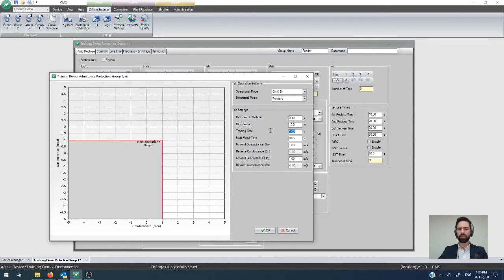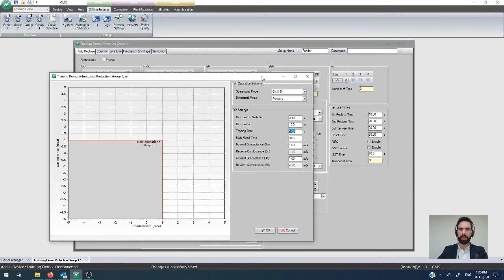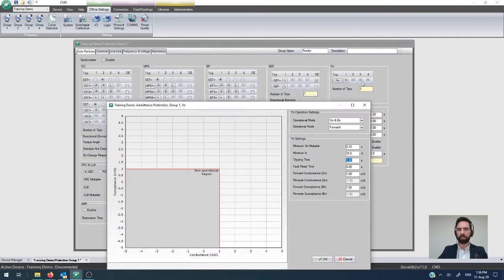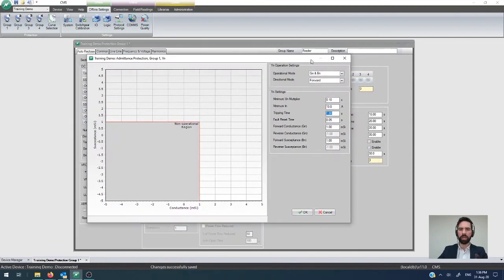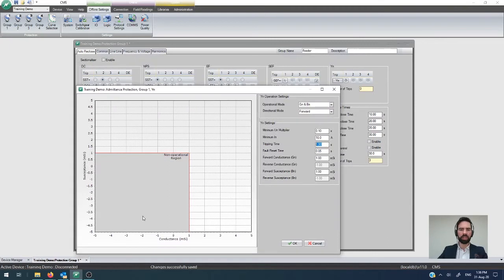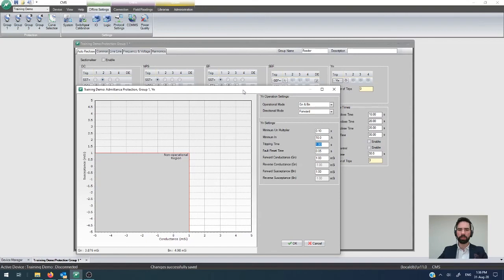You can set your tripping time. There's only one that you can use across all of the four sets of the operations and you'll see there's no directional element tick box because the directionality is calculated based on the vector quantities, i.e. the forward conductance, reverse conductance, forward susceptance and reverse susceptance.